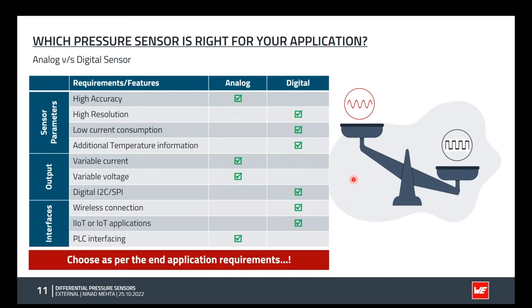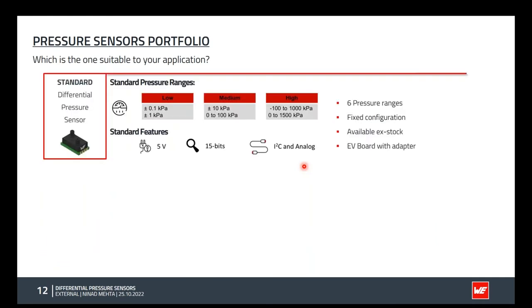Let's now have a look at some of the pressure sensors we have in our portfolio. So we have as a standard differential pressure sensor, in low, medium and high pressure ranges, which starts from ±0.1 kilopascal to 1500 kilopascal. These sensors work at 5 volts, and they have 15 bits of ADC resolution, and the sensors are I2C and analog. So digital I2C and analog output, both of them are available in parallel. So you can either choose to read out the data with the digital interface or also have an analog output.